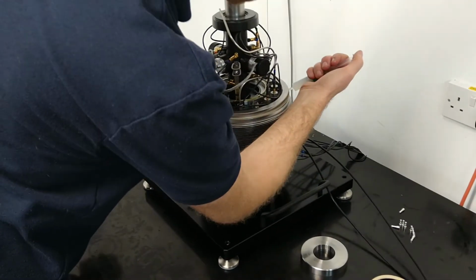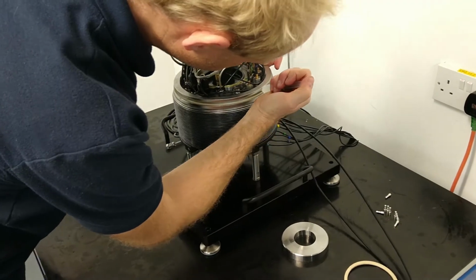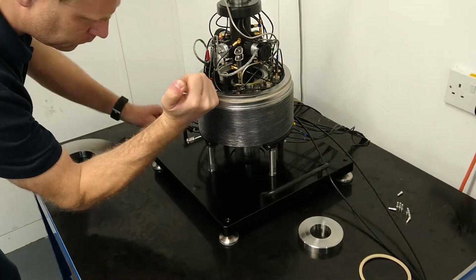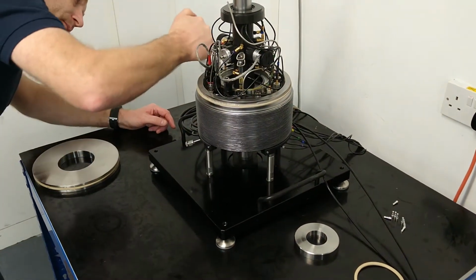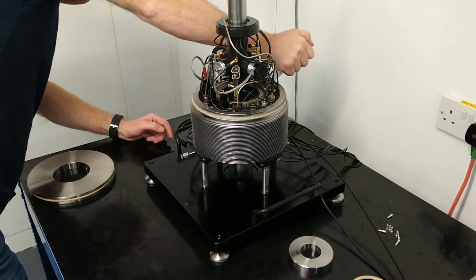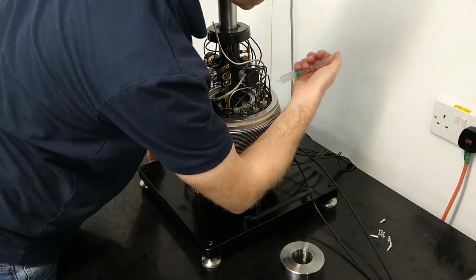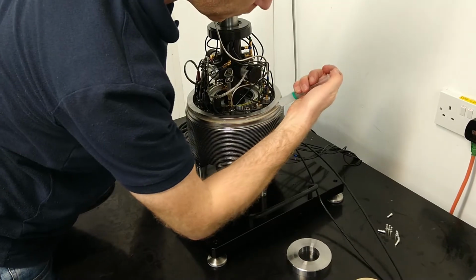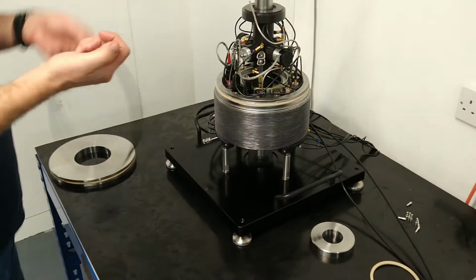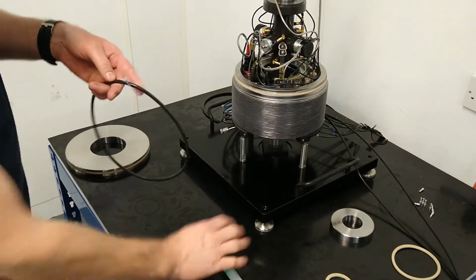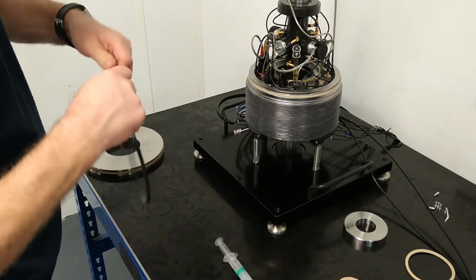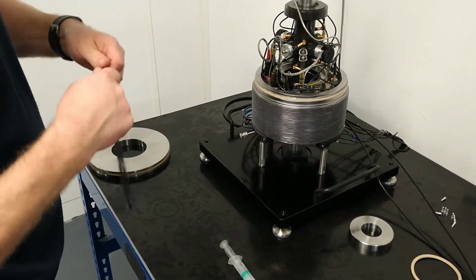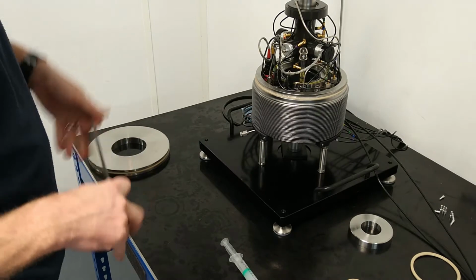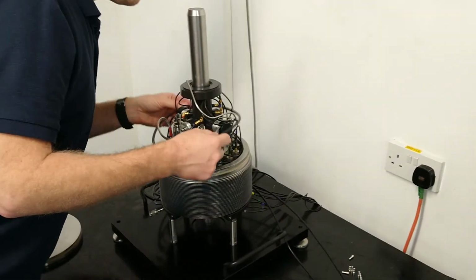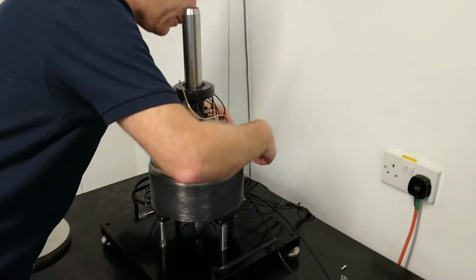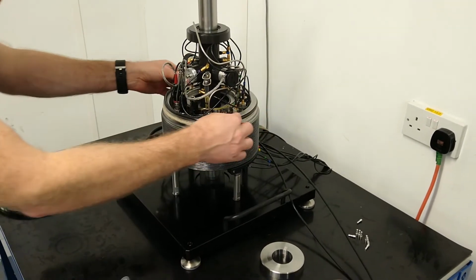Apply silicone to the top surface of the backing ring and the O-ring. Each time the cell is rebuilt, a new O-ring should be used in both the upper and lower sealing grooves. This is to maintain the sealing efficiency of the cell. Place the O-rings in each of the sealing grooves, making sure the backing ring stays firmly in place.